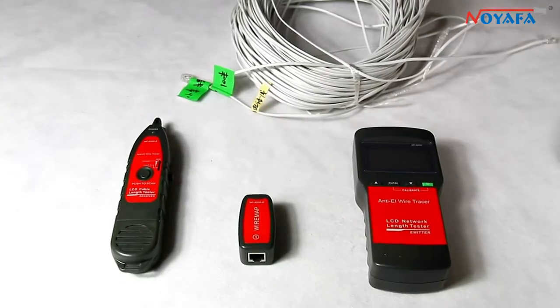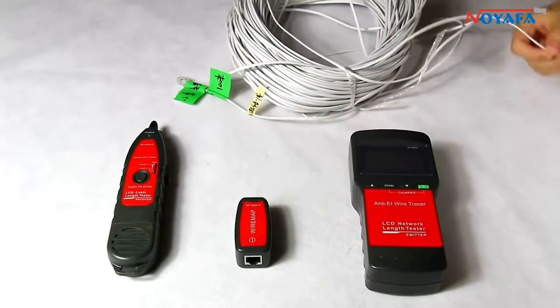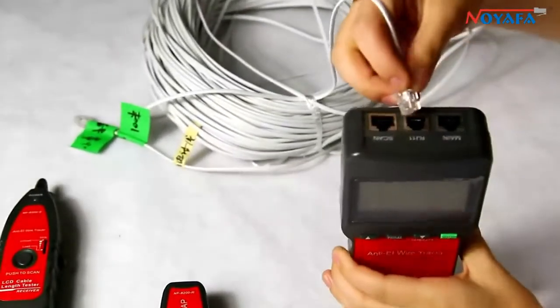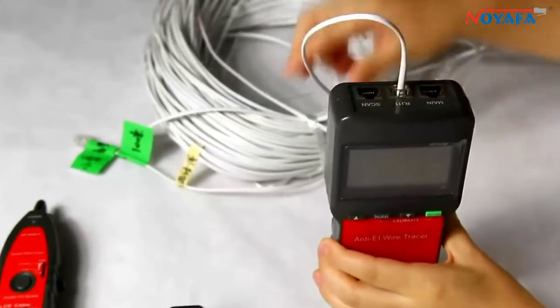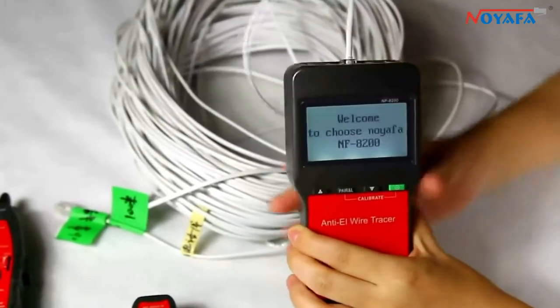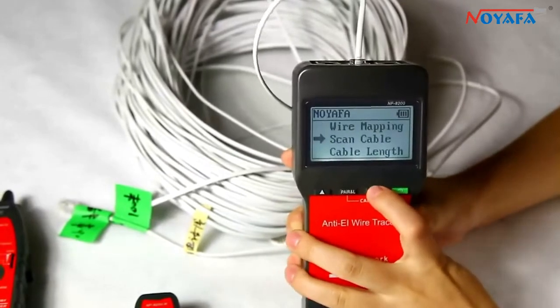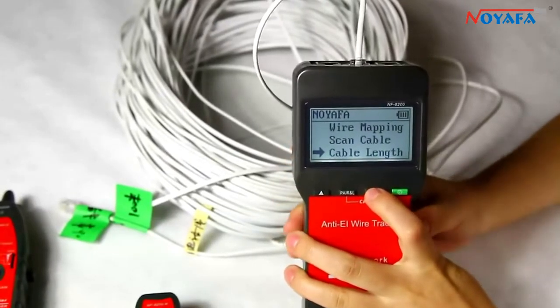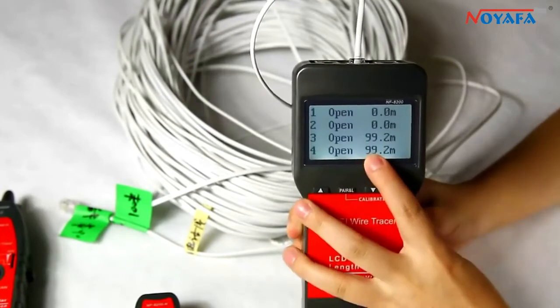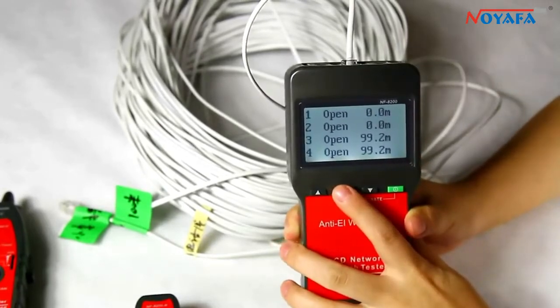Now we are going to measure cable length for a 2-core telephone cable, which is 100 meters. Connect one end to the RJ11 port of the emitter. Turn on the tester, here we choose RJ11, and we choose the cable length function. The result shows this cable is 99.2 meters, which means we need to calibrate it.